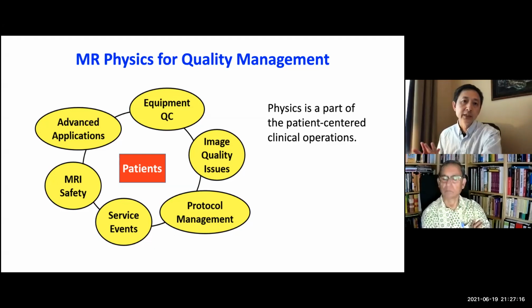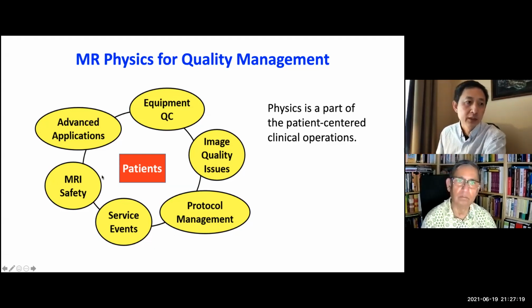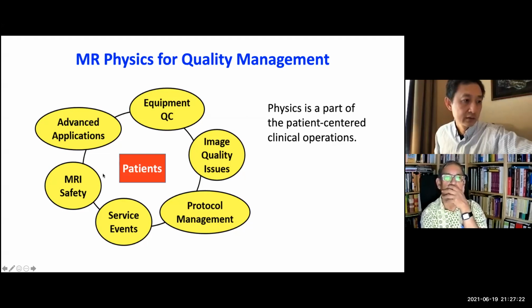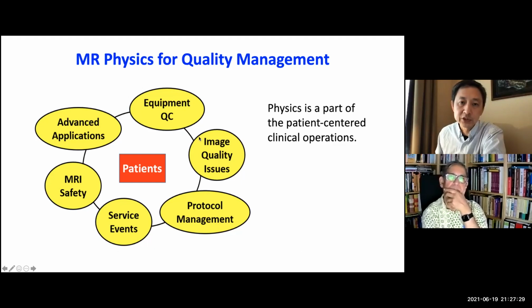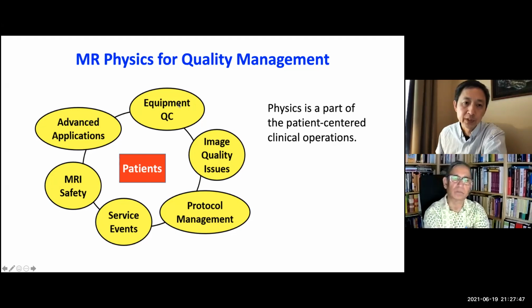Quality control testing is not everything for quality management. Here I list the different components of quality management. Equipment QC is what I just mentioned. But even with all of the QC testing, there will be image quality issues. Also, MRI has so many protocols, and an image quality issue can be related to protocol. It can be related to QC, meaning an equipment issue. It can be technical errors, many different kinds of issues. And also service events. Service usually makes things better, but can sometimes cause issues.